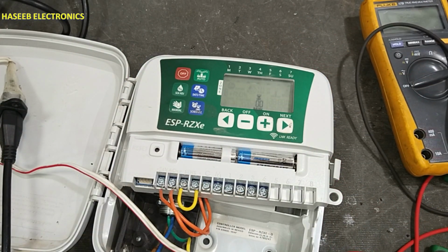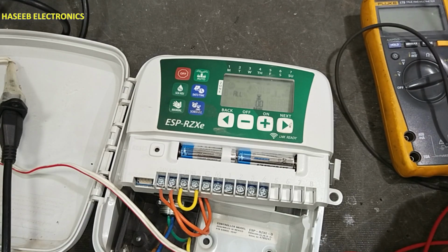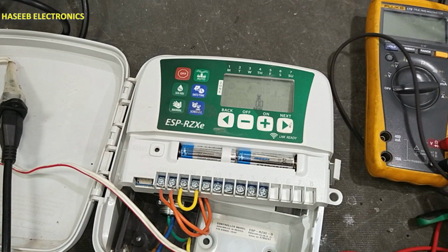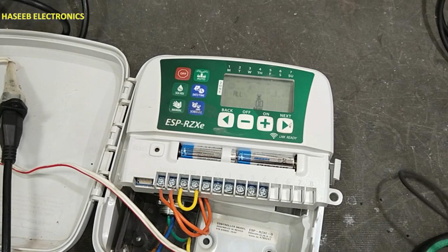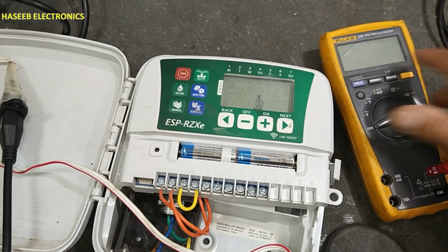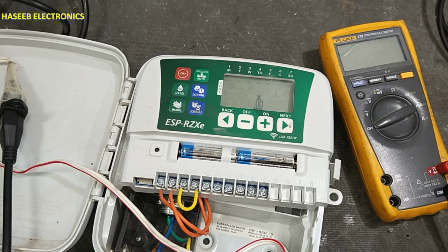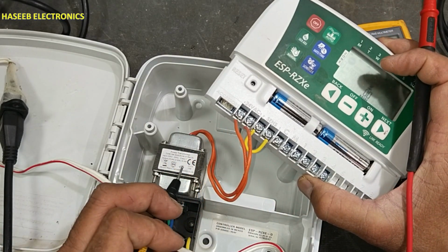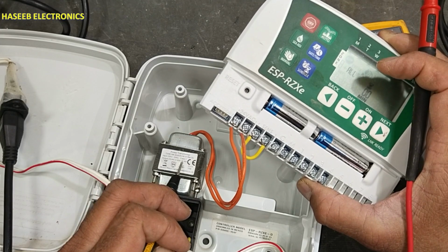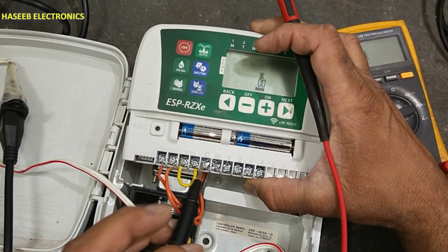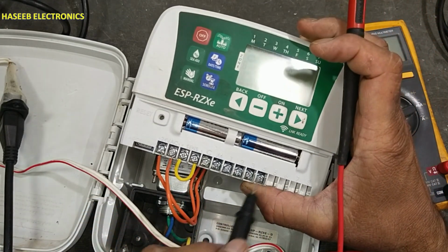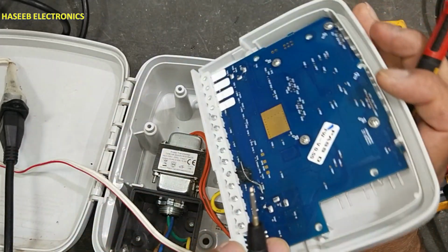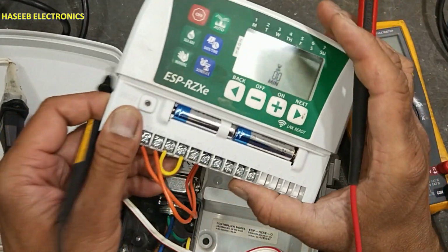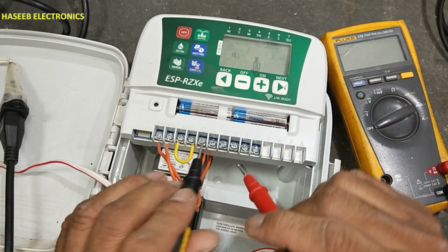It has a very small transformer. I don't know the reason why it is damaged. Might be there is something wrong, because normally it is just a 15.6 watt transformer, 0.65 ampere. If the track is burned out, that means there is some wrong connection or something like that.